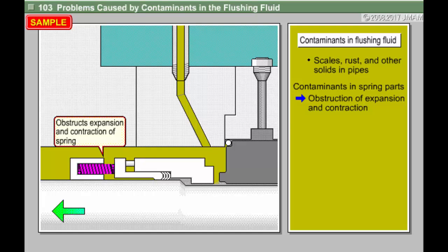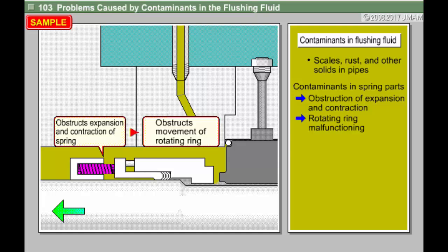And if the shaft then moves in the thrust direction, such as when the pump starts up or shuts down, the rotating ring also moves along with it. As a result, a gap develops in the seal surface and massive leakage occurs.